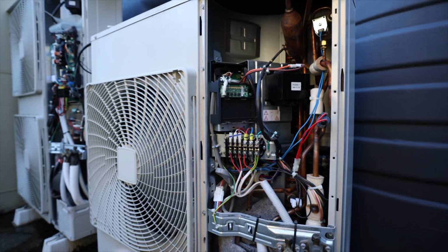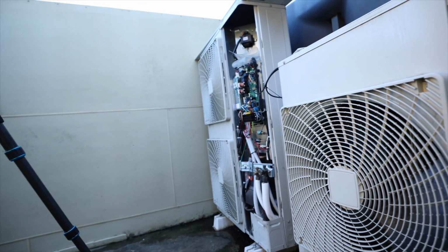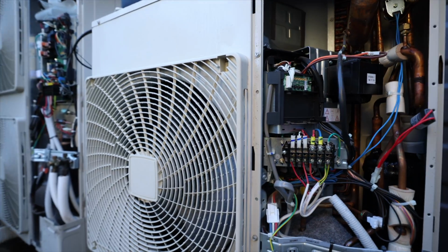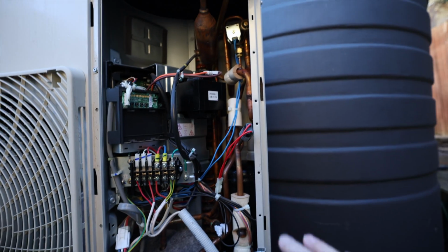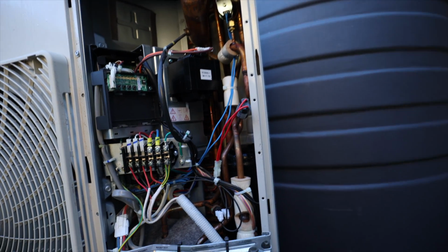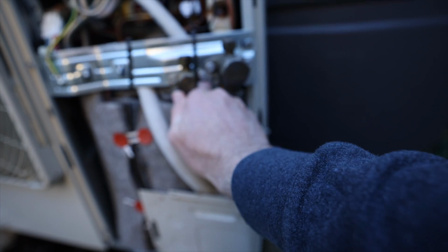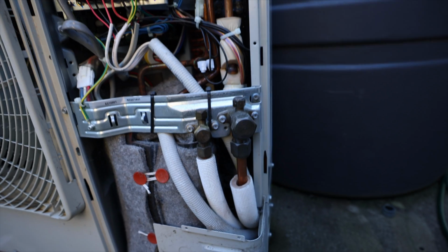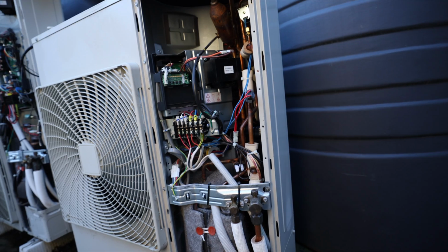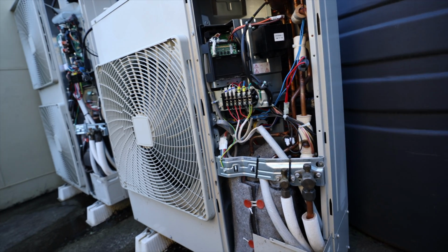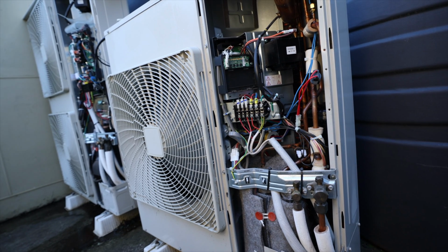So you come to the outdoor unit, you can probably hear that one still running, and it's not far off a defrost either. But this one is still making noise, the compressor's running, the fan is off, sending the cold gas inside through these two pipes. These two pipes will now become quite cold, and the hot gas is going to the outdoor unit. This takes about 10 minutes, maybe 15 usually.